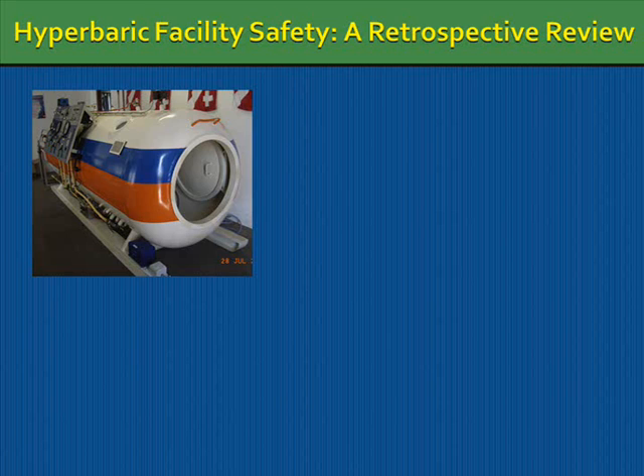Just a couple of pictures again to show you what we're looking at. You'll see this is very typical here of a remote recompression chamber, a typical deck decompression chamber. I would say of all the multi-place chambers around the world, probably the most common remote type chamber you get. Not very comfortable, not very pleasant spending four and a half hours inside a chamber like that. And Franz has been to Zanzibar, where that's located. At the stage it was installed, there was no air conditioning, and the outside environment is about 35 degrees. Inside the chamber, 38, 39 degrees, really not ideal for an effective treatment.